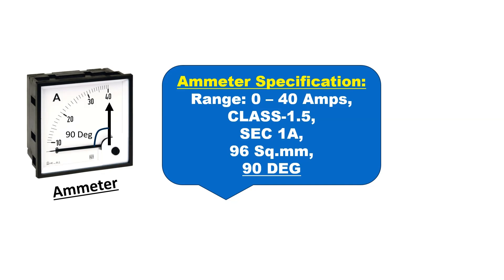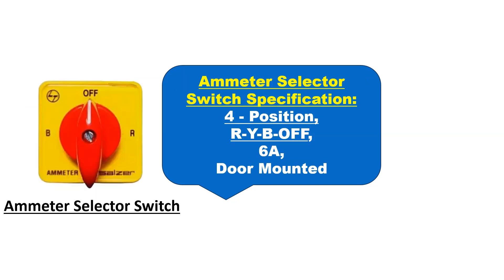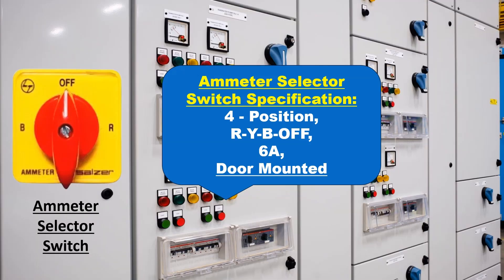96 square mm indicates the physical dimensions of the ammeter's front panel. 90 degrees means the display is intended to be read at a 90-degree angle from the standard position, which is important for panel mounting and ensuring the meter is viewed from the correct angle. For the ammeter selector switch: 4 positions means there are 4 selectable options — R, Y, B, and off. 6A means the selector switch can handle a maximum current rating of 6A. This selector switch is designed to mount on the door of an electrical panel, hence it is mentioned as door mounted.